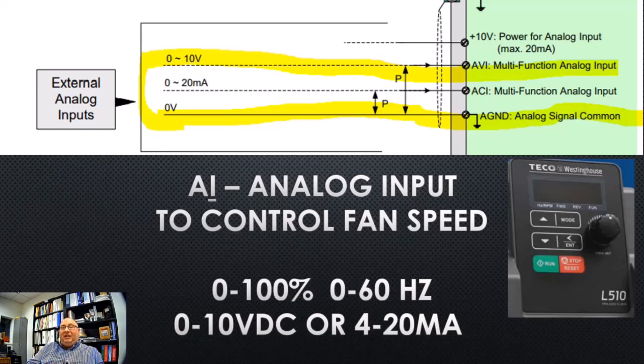A lot of times the fuses get blown and you don't realize it, and you're working with a meter with a blown fuse on the milliamp side, and you're really going down the wrong path. You're doing more damage than good. So if you could use 0 to 10 volts DC, it's a lot easier to troubleshoot, and it's a lot easier and more convenient to work with. All right, but there are some advantages to why we use 4 to 20. It's because it could go longer runs and it has less EMF interference. But if you're working in the confines of like 50 feet or less, you're fine.